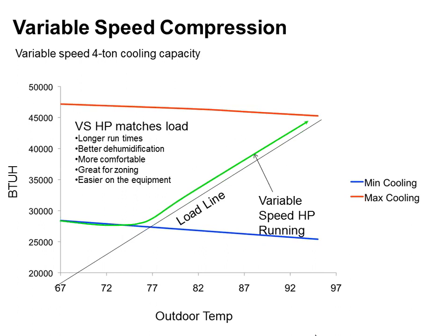And if we draw parallels to our commercial variable speed compression systems that we've been using, like on the Panasonic and Sanyo VRF systems that we've been doing for the past 3.5 years, we've had 0 compressor failures on one of these Sanyo Eco-i VRF systems that we've been doing for 3 years. Not a single compressor has failed on a job in the Chicago area that we have done. I'm sure I just jinxed somebody's job site, but we bought 0 replacement compressors for these variable speed systems commercially. I imagine the same story is going to happen residentially. Things last longer when you modulate them than when you bang them on and off.